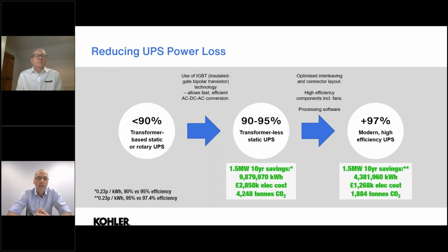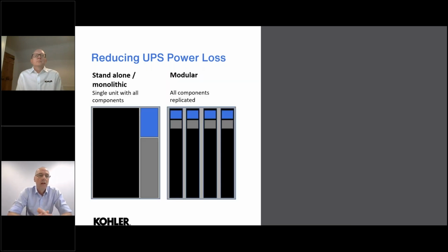And so we can see that very small percentages in the efficiency do make a significant difference in the amount of power that we are wasting with the UPS. And then we wanted to sort of smart size the UPSs. Typically, UPSs will come as standalone monolithic systems. All the units have single unit components, so one inverter, one rectifier, one battery. And we have the modular systems where all the components are replicated, typically in slightly smaller modules.